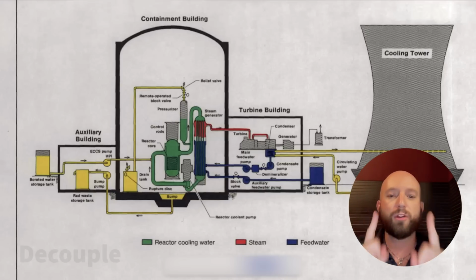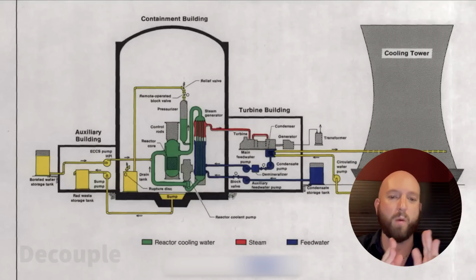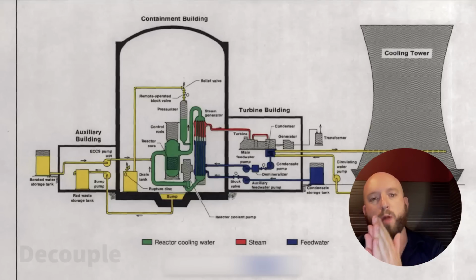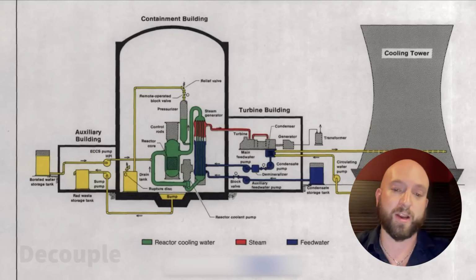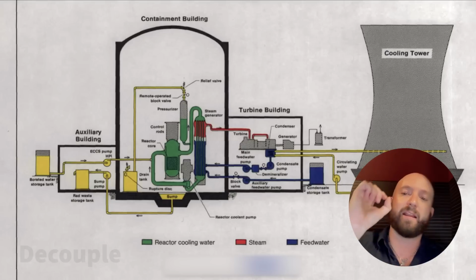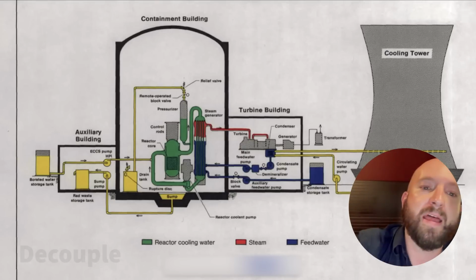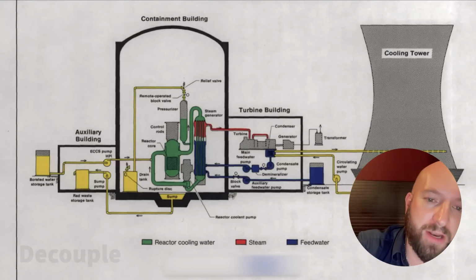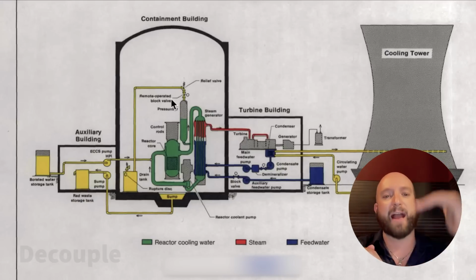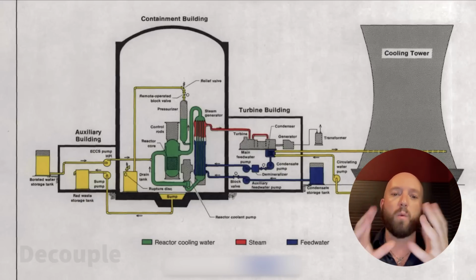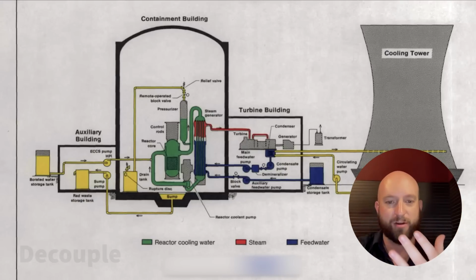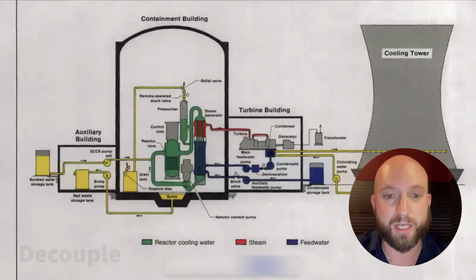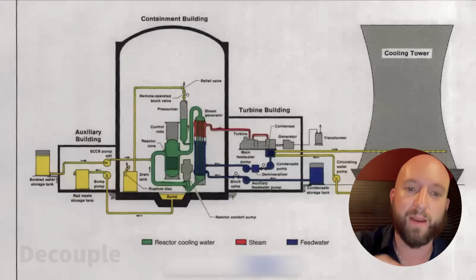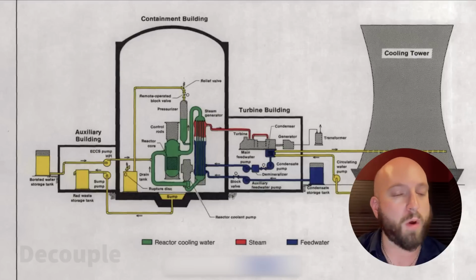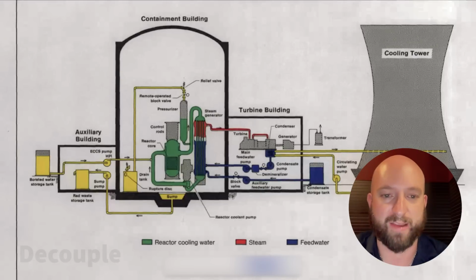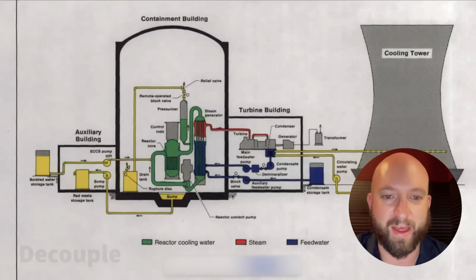And the critical thing to understand, and this is the beginning where we start departing from a regular sort of anticipated occurrence into an accident, is that the light in the control room that indicates what the position of this valve is does not indicate the actual position, but rather whether that solenoid is energized or not. The solenoid is de-energized, so the light goes out in the containment, but that valve is stuck open. So we're only seconds in to this transient. So I want to pause there.